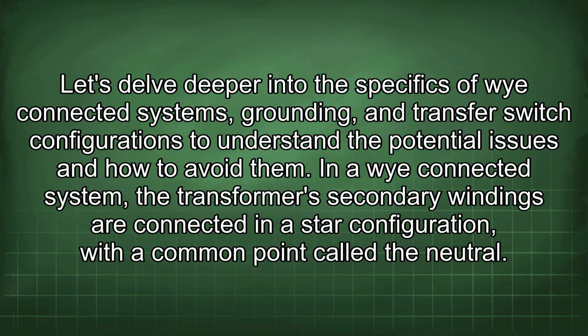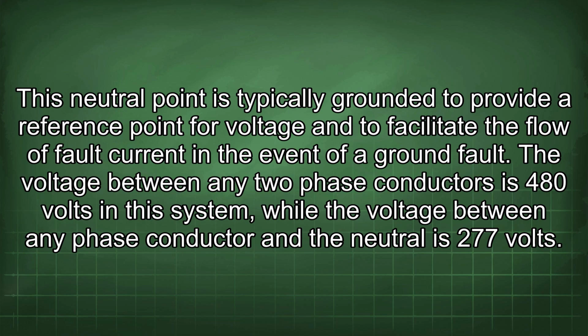In a Y-connected system, the transformer's secondary windings are connected in a star configuration with a common point called the neutral. This neutral point is typically grounded to provide a reference point for voltage and to facilitate the flow of fault current in the event of a ground fault. The voltage between any two phase conductors is 480 volts in this system, while the voltage between any phase conductor and the neutral is 277 volts.